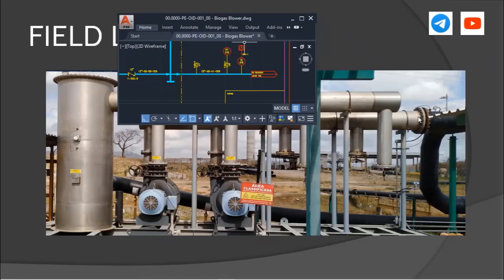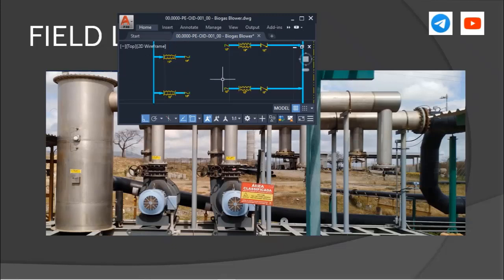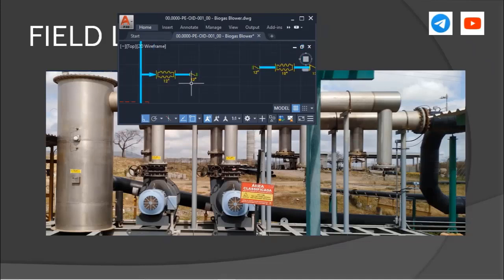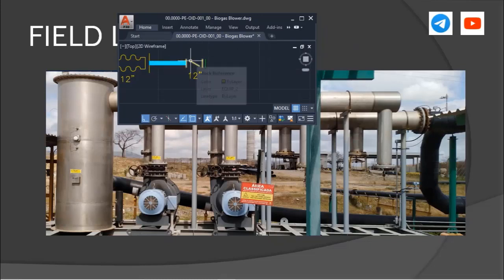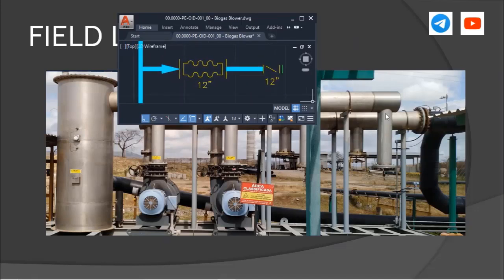And so the battery limit of this skid is this flange, and we have a flange also behind the separator vessel. We cannot see here, but we'll have a flange there also. And observe that the spares in the P&ID tells that we already have a junction expansion and a 12-inch valve. This valve representation for this project is a butterfly valve. However, in the field, we don't have that. We have only a spare with a blind flange and a tap for a drain.